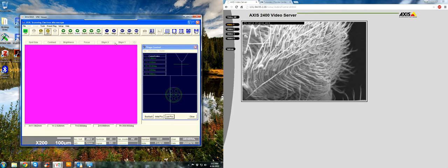Okay. Now let's say you're satisfied with the image quality. You've adjusted the focus, the brightness, the contrast, and you really like this. We're currently in scan 2, which is a TV scan rate. We can move to scan 3, which is a slower scan rate, and you can see how it adjusts on the video screen slowly. The beam scans the area, rasters the sample slower, so it takes longer to pick up the image, but it gives you higher pixel density.